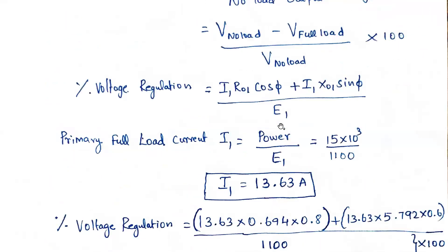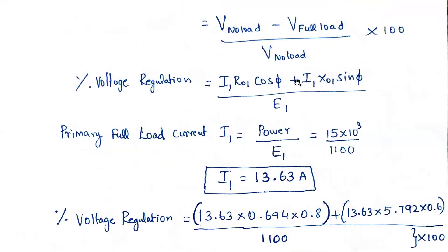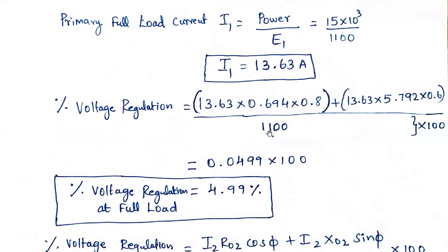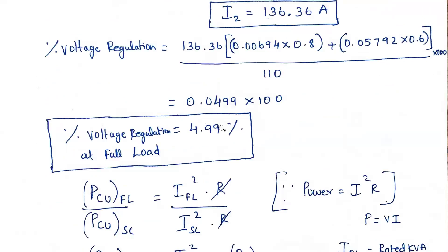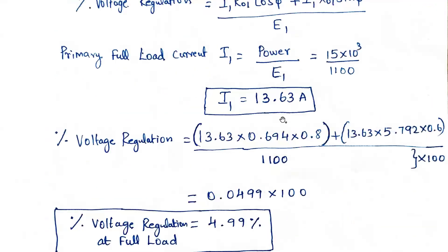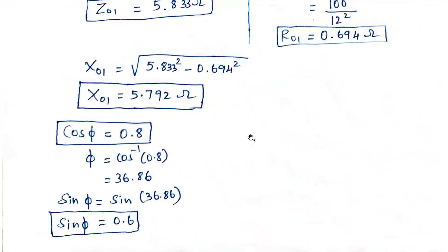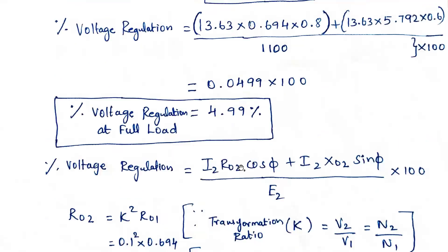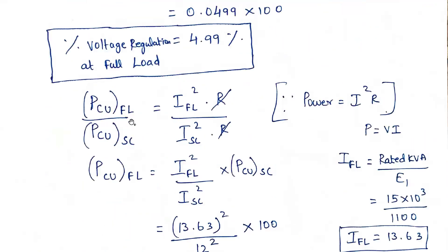So with respect to secondary we also got 4.99%, the same as with respect to primary. This confirms that either approach gives the same result. Since all data were given with respect to primary, calculating from the primary side is sufficient.